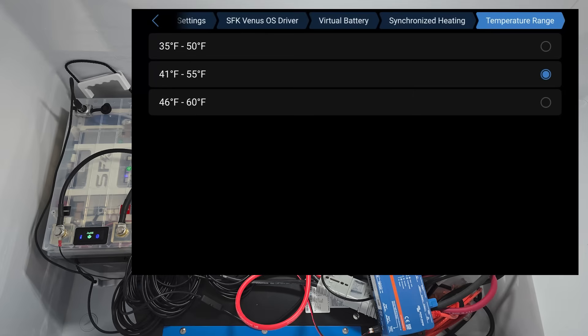Now, the reason we have a range is we're not just dealing with one battery. We're dealing with multiple batteries. And since we're turning heaters on and off, not all batteries are going to charge up or heat up equally, but they're all be using power. So we want to keep our power draw universal across all of the batteries. That's why we have a range. For this test, we'll keep it at 41 to 55. I think that's going to be a good solid number.